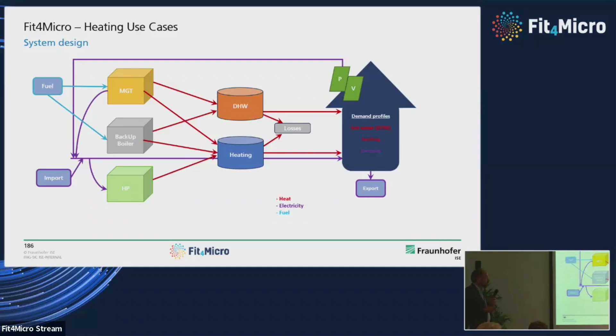With rough considerations, we found that to achieve many full load hours, which is required especially for the microgas turbine to run efficiently and cost-effectively, you should look at places with a year-round need of heat, such as the health sector or old folks' lodging, where besides space heating there's also high demand for domestic hot water.